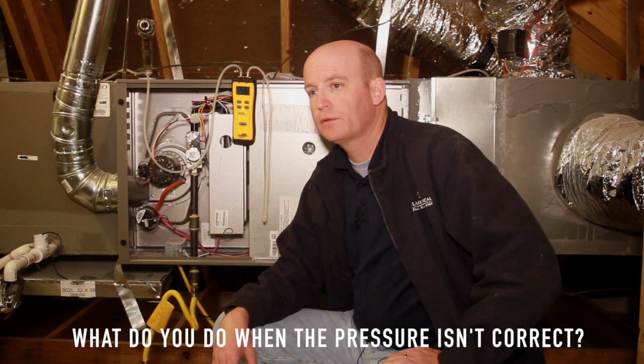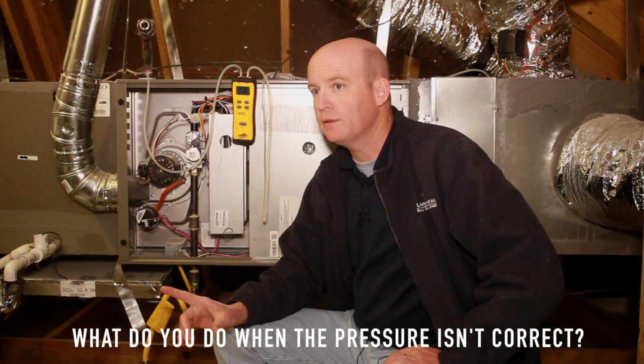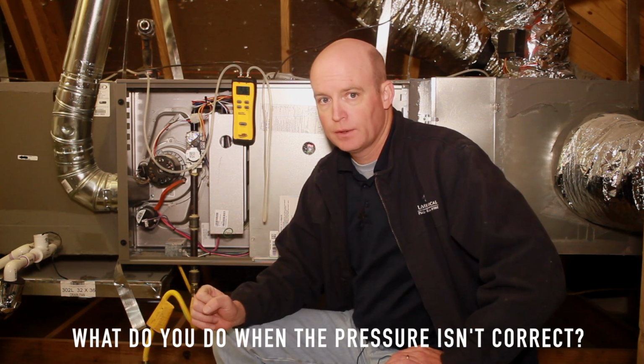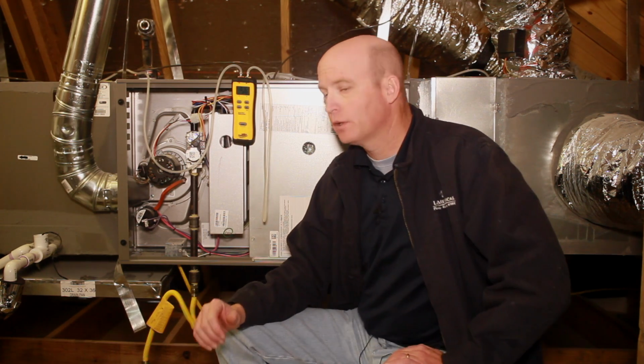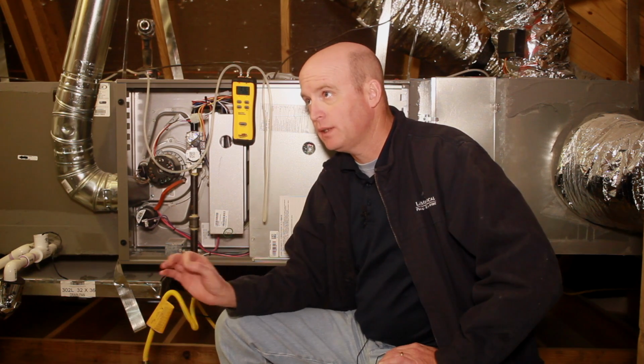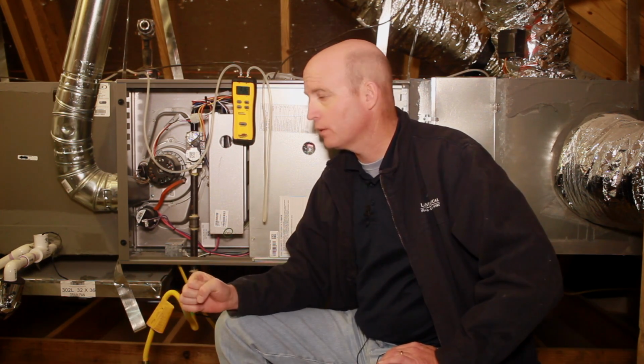We're going to look for kinked ductwork. We've taken the filter out of the equation. The filter is always pulled during this test. So probably our biggest issue would be kinked ductwork. Perhaps some of the install crews left film on one of the registers or on a return.